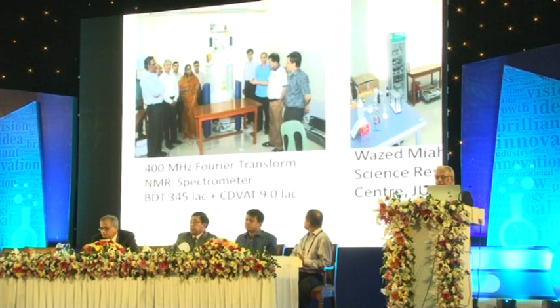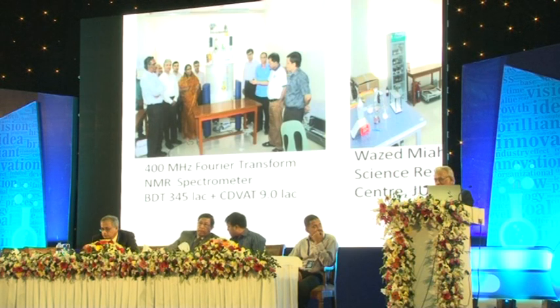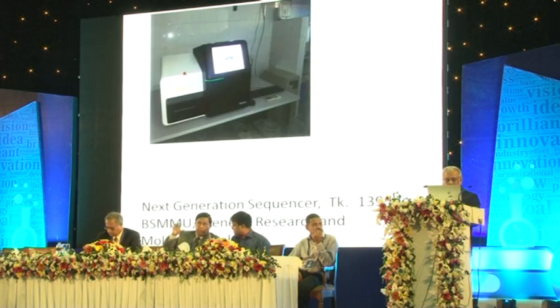One filling of liquid helium costs about 10 lakh. You have to bring an expert from India, you have to bring liquid helium from India, and you need a filling every 8 months. So this is what you need if you want to sustain this thing. But without this, you cannot do modern research in chemical sciences and biological sciences.